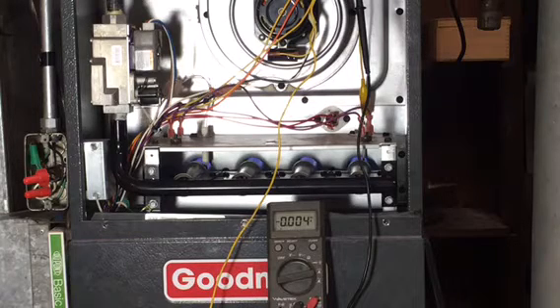You can hear it runs at a low speed versus a two-stage furnace. So everything's checking out so far. The other part of this is the combustion analysis, which is a whole other deal. I put a probe in here with an instrument and measure a whole bunch of things like carbon monoxide in the atmosphere and CO2 and things like that. Well, we'll continue that later.